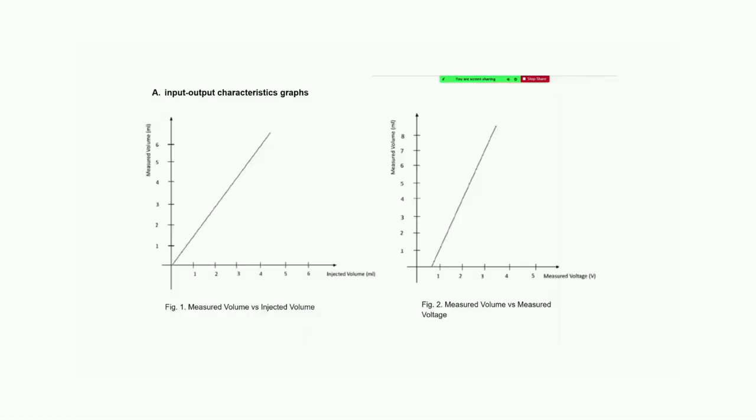So, these are our input-output characteristic graphs. The first graph is for measured volume versus injected volume and the second one is for measured volume versus measured voltage. So, we can reverse this data to actual limb segment data. There we input voltage and we can get the volume measurement from these graphs and we can say whether they have any abnormalities.